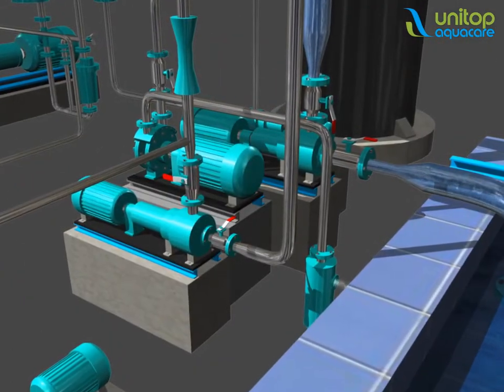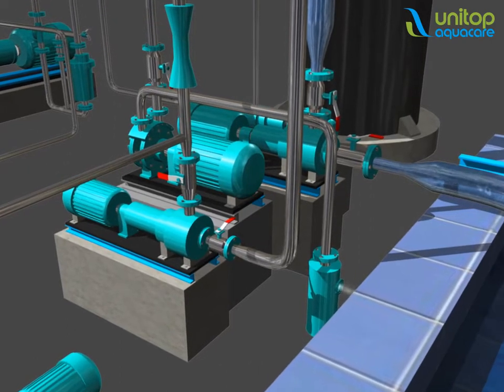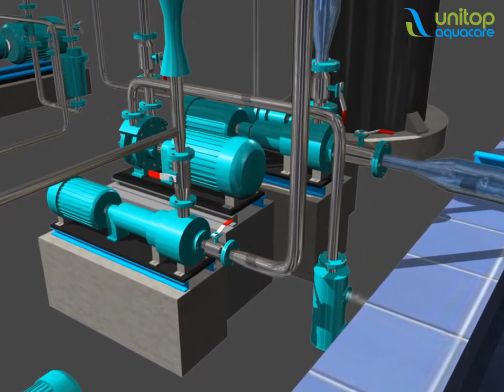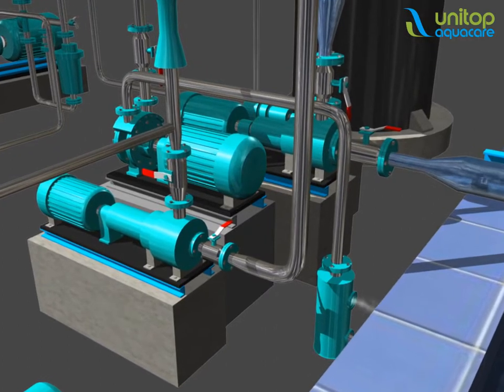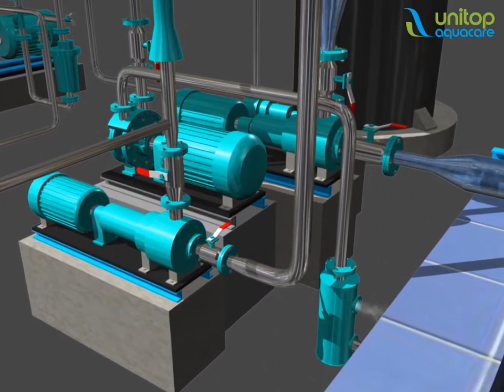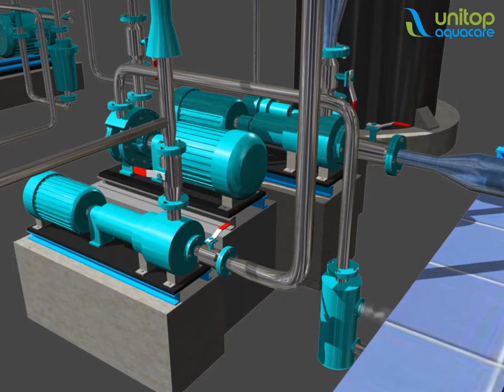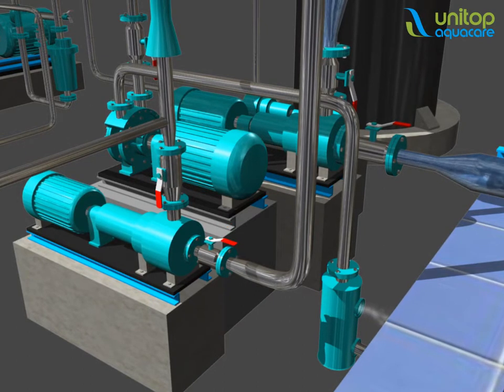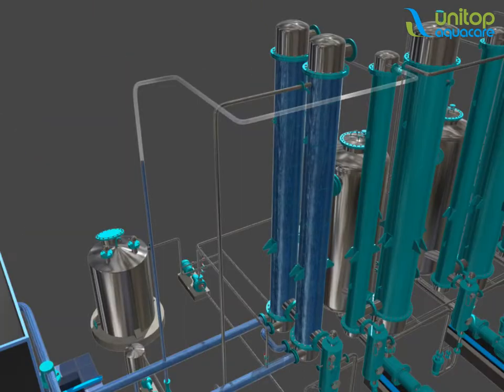Process description for multi-effect evaporator: Start the adiabatic evaporator and apply vacuum in the system by water ring pump. Then start the feed pump. The feed flows through a series of preheaters.